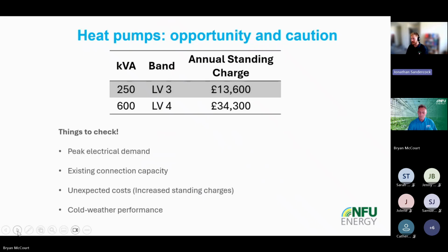So just to give a representative idea of what that would mean on paper, if you were, for example, with a connection of 250 kVA, here we can see the impact of upgrading to a 600 kVA connection when accounting for the additional heat pump that was to be installed. You can see that you would jump up from band 3 into band 4, and then also with the additional capacity charges that you've got to pay, you're looking at fixed costs in excess of an additional £20,000 per year moving forwards.